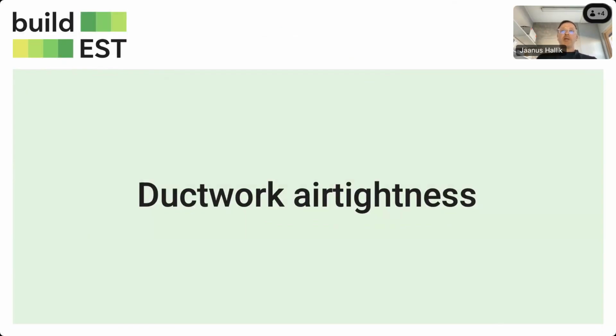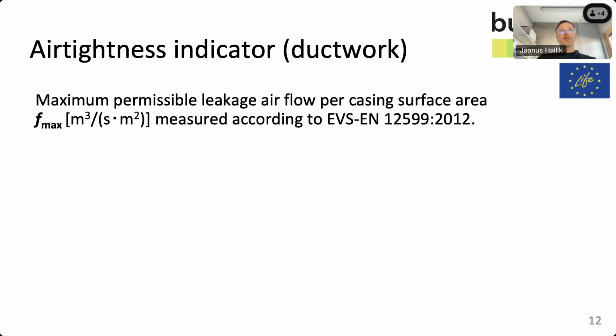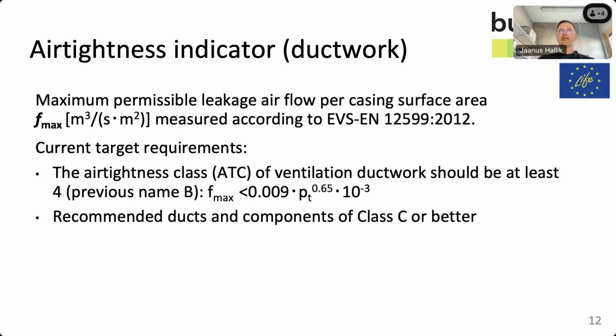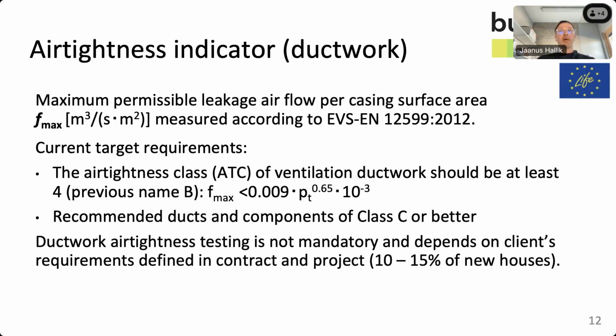And about the ductwork airtightness, as I mentioned, it's not really studied a lot in Estonia. As the airtightness indicator, we have the maximum permissible leakage airflow per casing surface area, fmax, measured according to the standard 12599. And current target requirements are that the airtightness class of ventilation ductwork should be at least 4, with the previous name of B. And recommended ducts and components should be of class B, C, or better. But the ductwork airtightness testing is not mandatory and depends on the client's requirements defined in the contract and the project. So basically, the designer selects components, proposes a level in the contract, and then it's an agreement from the client.